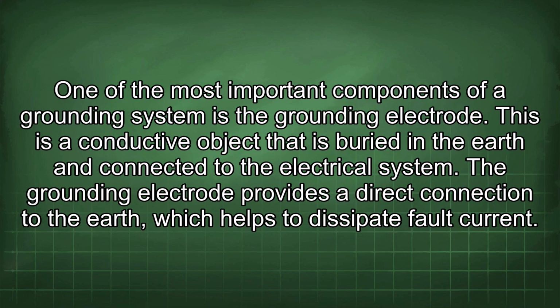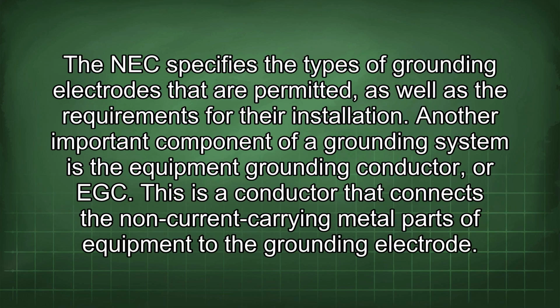One of the most important components of a grounding system is the grounding electrode. This is a conductive object that is buried in the earth and connected to the electrical system. The grounding electrode provides a direct connection to the earth, which helps to dissipate fault current. The NEC specifies the types of grounding electrodes that are permitted, as well as the requirements for their installation.